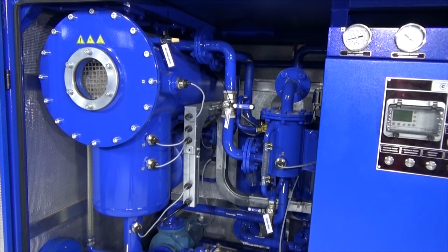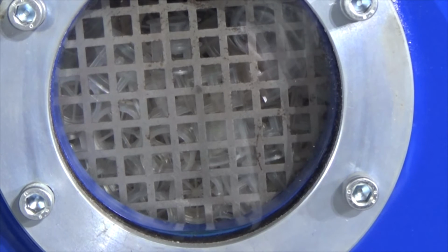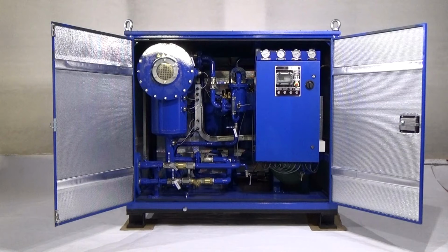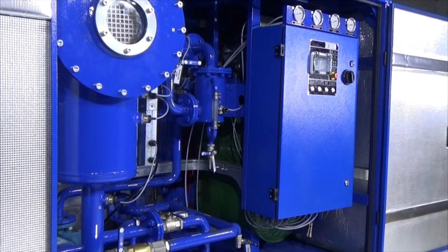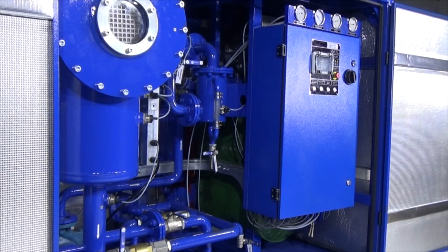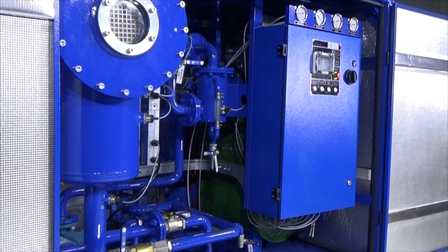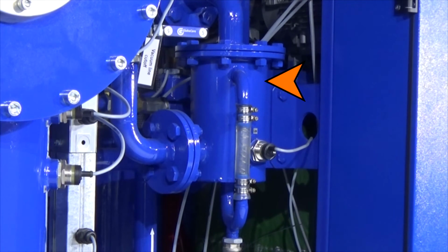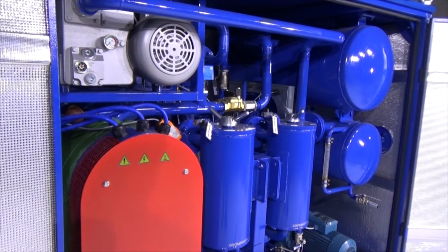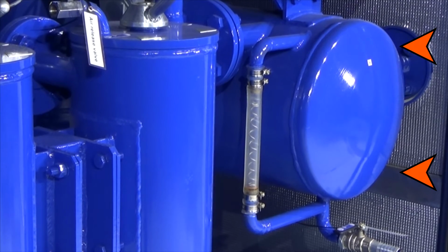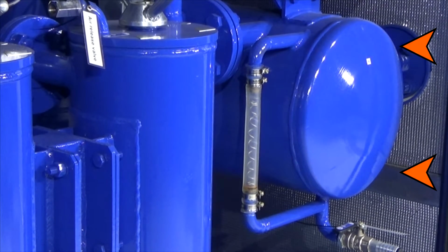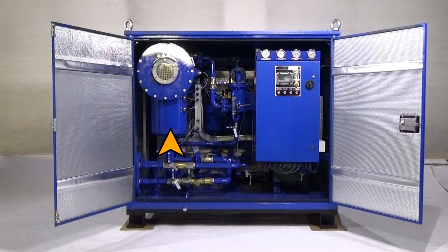In the chamber, the oil flows from the distribution device through polypropylene rings. When the oil flows down through the rings, it forms a very thin film on the surface of the rings. Vacuum reduces the partial pressure of water, causing rapid evaporation. Moisture passes through the oil trap and the vacuum pump into the condensation vessel, where it accumulates for subsequent disposal. Processed oil accumulates in the bottom of the vacuum chamber.